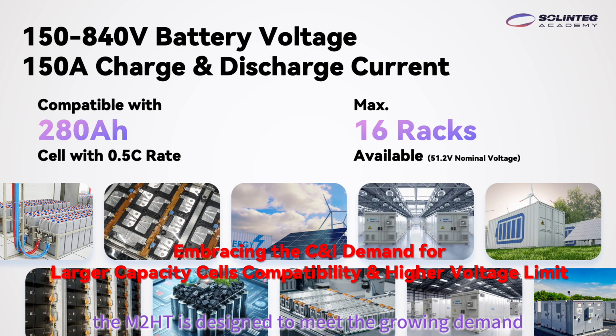The M2HT is designed to meet the growing demand for larger battery capacity in C and I applications. With a battery voltage range of 150 to 840 volts and a maximum charge and discharge current of 150 amps, it pairs well with the 280 ampere-hour and 314 ampere-hour cells commonly used in commercial projects today, delivering strong system performance at a 0.5 C rate. The wide voltage range also means the system can support up to 16 battery racks in a single string at 51.2 volts nominal, giving installers the flexibility to scale storage capacity to match the site's energy demands without adding complexity.